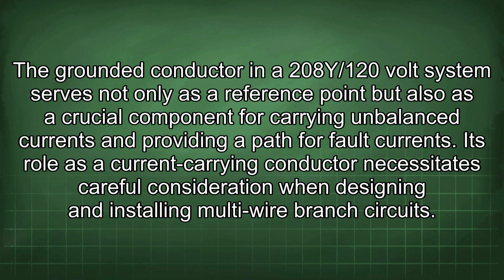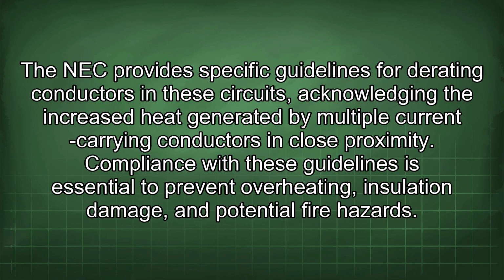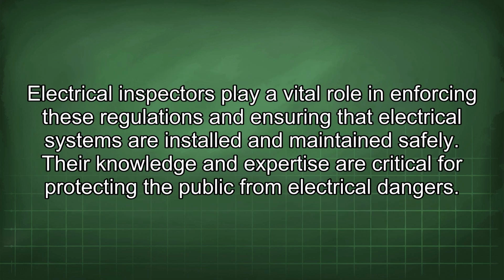The grounded conductor in a 208Y/120 volt system serves not only as a reference point but also as a crucial component for carrying unbalanced currents and providing a path for fault currents. Its role as a current-carrying conductor necessitates careful consideration when designing and installing multi-wire branch circuits. The NEC provides specific guidelines for derating conductors in these circuits, acknowledging the increased heat generated by multiple current-carrying conductors in close proximity. Compliance with these guidelines is essential to prevent overheating, insulation damage, and potential fire hazards. Electrical inspectors play a vital role in enforcing these regulations and ensuring that electrical systems are installed and maintained safely. Their knowledge and expertise are critical for protecting the public from electrical dangers.